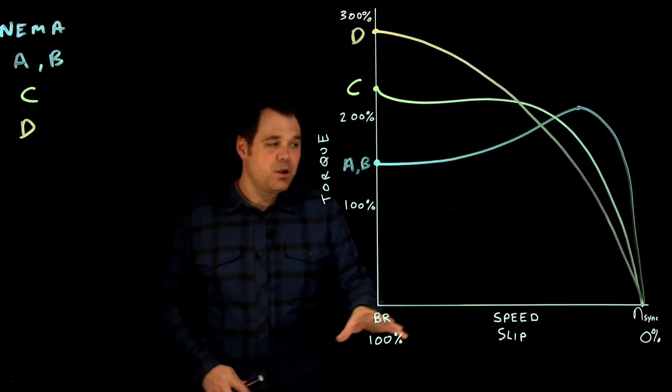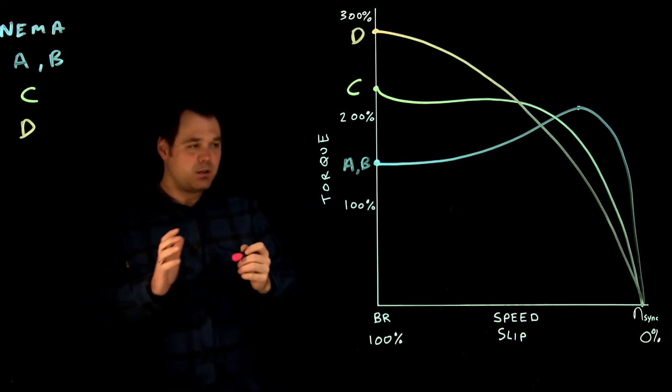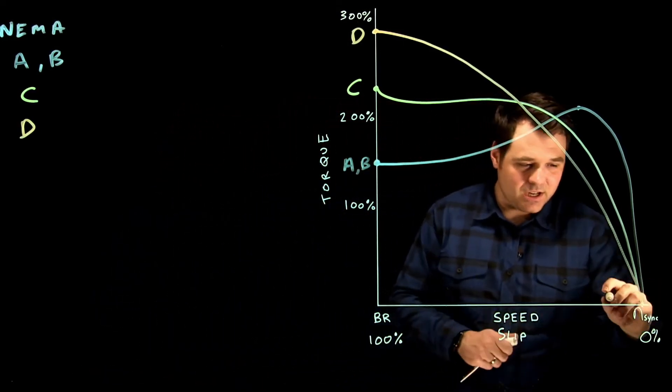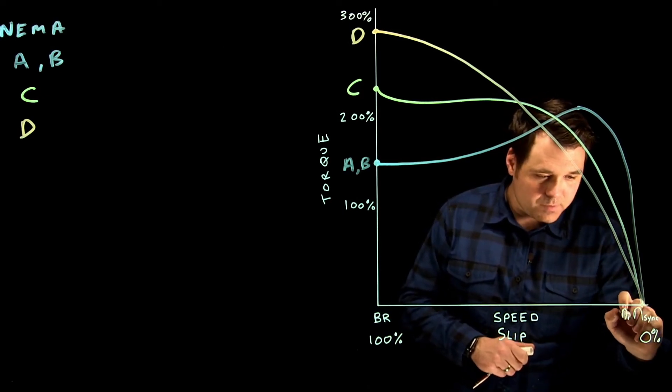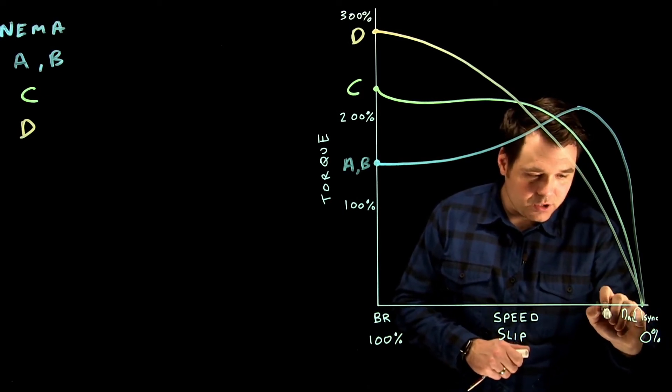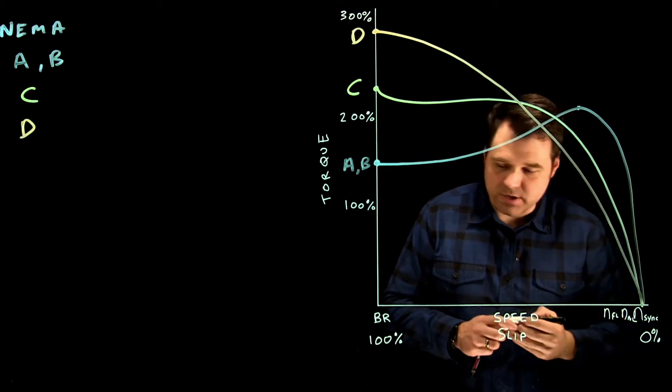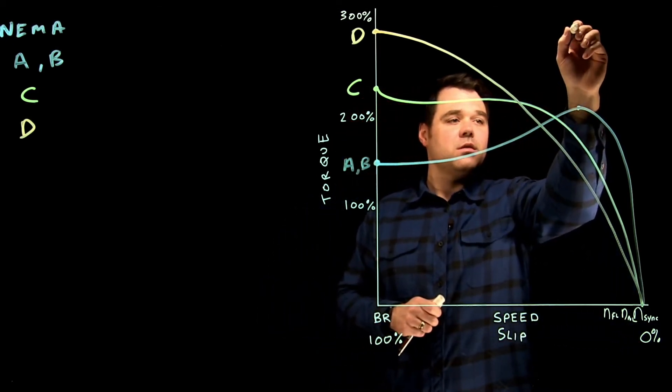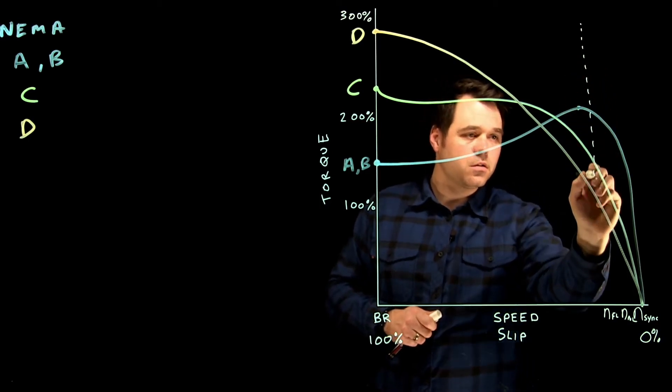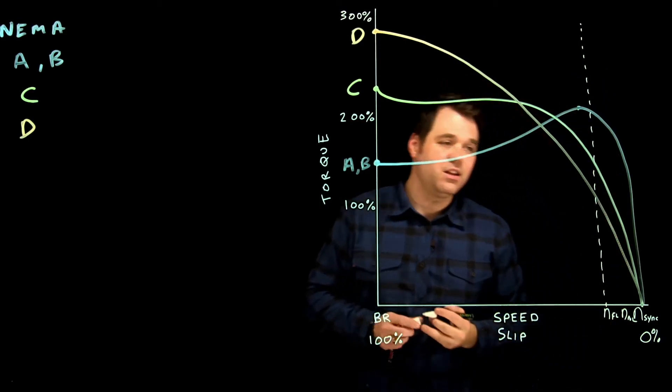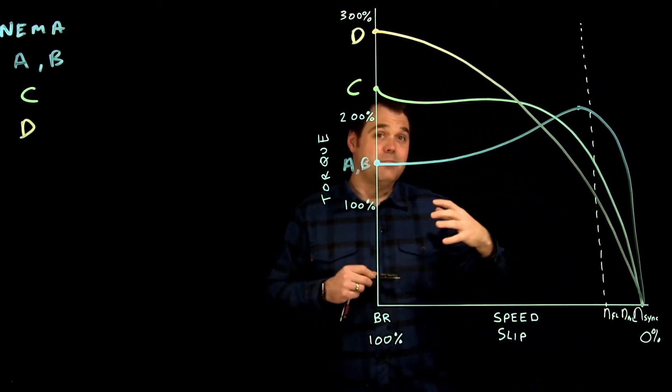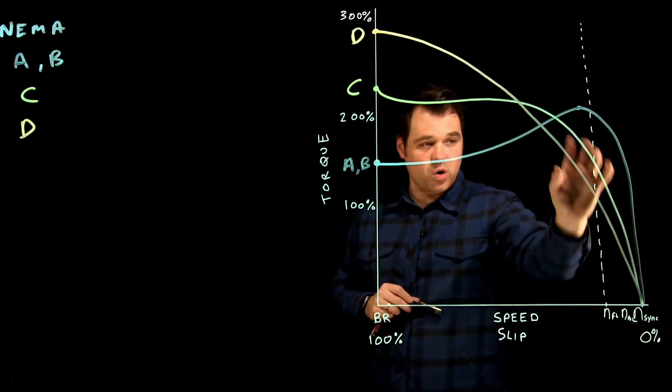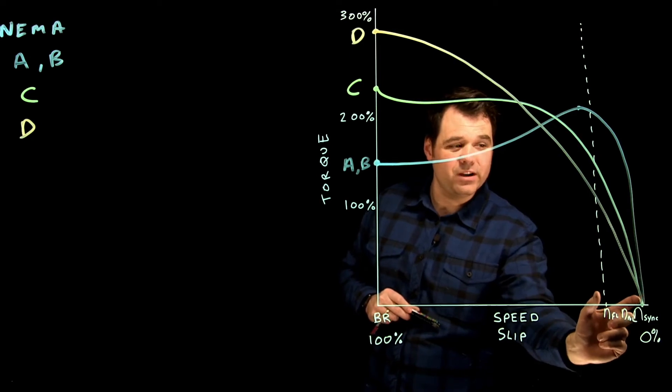Now, I want to stop here for a second. We got to think about when we think about speed, our synchronous speed is here. Our no load speed is right there, and our full load speed is right there. So the actual operating range for a motor is right in here. That slip ends up being a very good representation of the torque curve in the operating range of a motor.